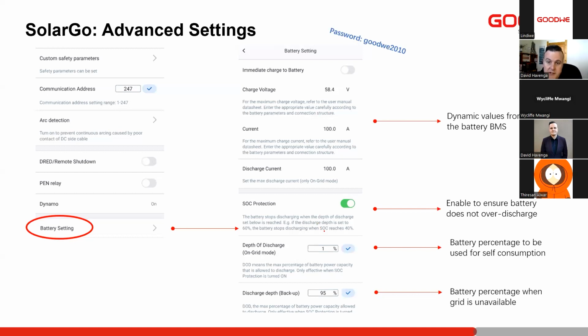Then we have SOC protection. This should always be on. This ensures that the batteries do not over-discharge and that the inverter listens to the battery when it stops charging or discharging. Here we've got two settings: on-grid depth of discharge and off-grid or backup depth of discharge.